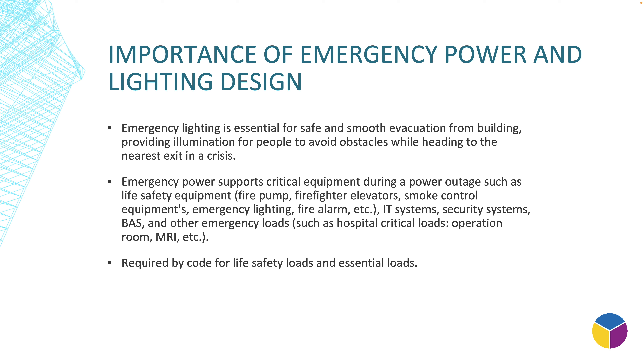First, we talk about why emergency power and lighting systems are important. For emergency lighting, we need that especially during emergency situations. Emergency lighting and exit signs can provide directions and minimum illumination for people to escape from the building. Emergency power is also very important because we need it for fire pumps, firefighter elevators, smoke purging systems, fire alarms, and emergency lighting — these are life safety loads.